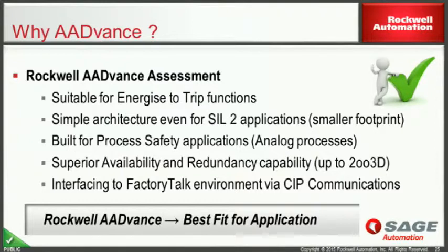So when we assessed AADvance, it is suitable for energized to trip functions. It has a simple architecture even for SIL2 applications, which also equated to a smaller footprint, which in some of our areas was quite an issue. It's built for process safety applications, so it's very good for analog processes. It had superior availability and redundancy above and beyond the other systems, up to 2 out of 3 with diagnostics voting architecture, which is the triplication architecture. Richard will go into that in a bit more detail later.